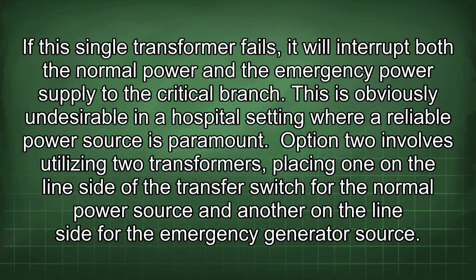If this single transformer fails, it will interrupt both the normal power and the emergency power supply to the critical branch. This is obviously undesirable in a hospital setting where a reliable power source is paramount. Option 2 involves utilizing two transformers, placing one on the line side of the transfer switch for the normal power source and another on the line side for the emergency generator source.